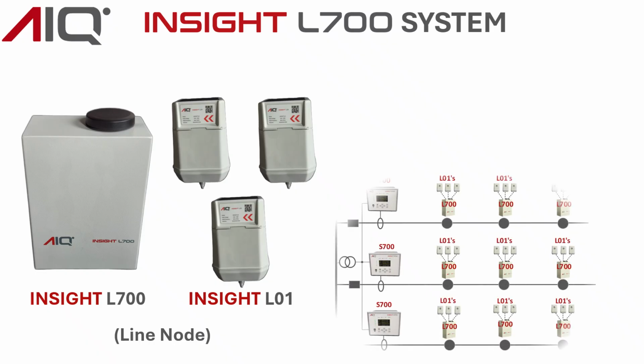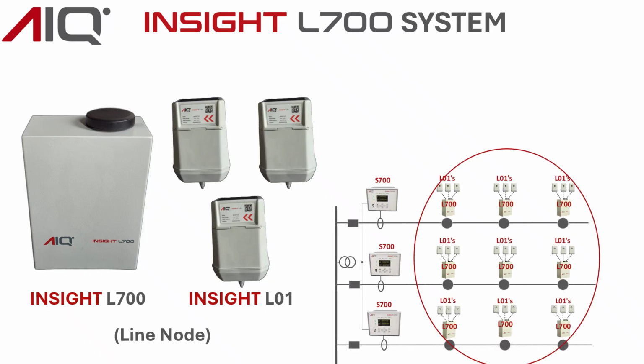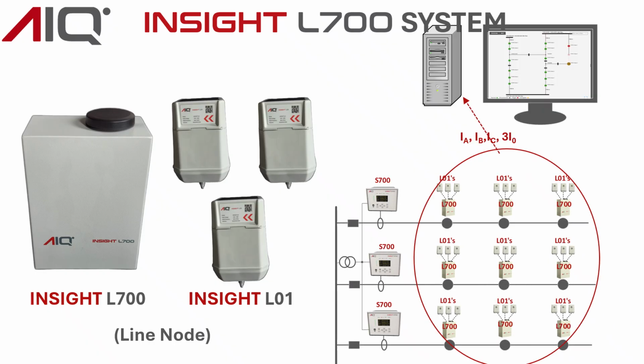This graphic shows that the triplets of sensors or nodes communicate via their local L700 to the server. These nodes are deployed throughout the network, and each node has 3 wireless CTs that sample current at 64 samples per cycle. Each line sensor communicates by short-range radio to its local L700 and then forwards the data to the master software for processing. Peripheral devices may be plugged into the L700, such as traveling wave modules for more accurate distance to fault values and wireless range extenders.